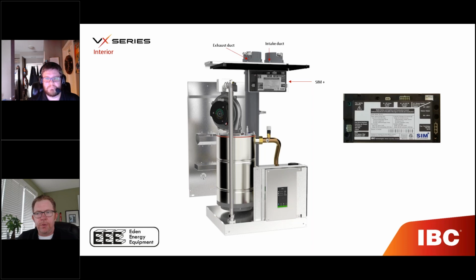It's got a lot of really cool features: low water cutoff, high limit manual reset, and independent temperature sensors - that's the vent stack, the boiler high limit, boiler supply, and boiler return. All that stuff we talked about with reverse flow, etc, is all monitored through this control. It's a really slick setup, so we're pretty excited to see this show up in the VX unit.